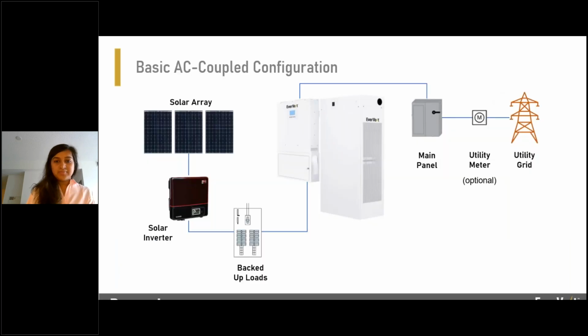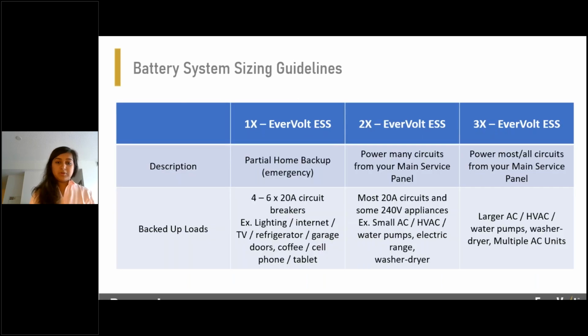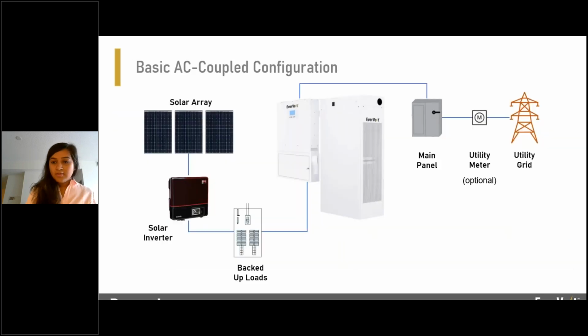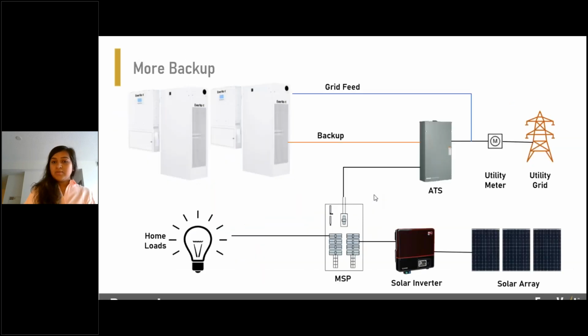Tony, next slide. Okay, great. This slide shows a basic wiring diagram for how the connection is made with an AC coupled system. If the customer has an existing solar array connected to a solar inverter, a PV string inverter, it would connect to the backed up loads panel, because the output coming from the PV array is in the form of an AC output. So that needs to connect to the Evervolt inverter through the backed up loads panel. And similarly, you would also do the grid interconnection with the system.